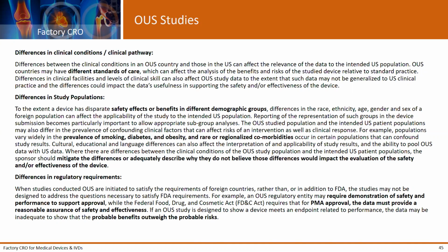The key thing that people need to understand is companies will get unsolicited case study information on a regular basis if they're doing good post-market surveillance. One of the first companies I worked at in medical devices had a hemostatic agent that some of our diabetic patients would insist the product healed diabetic ulcers. But the cost of doing a clinical study for wound healing to specifically target diabetic ulcers is extremely expensive, and the FDA has very high requirements for that kind of a study to make those specific claims.